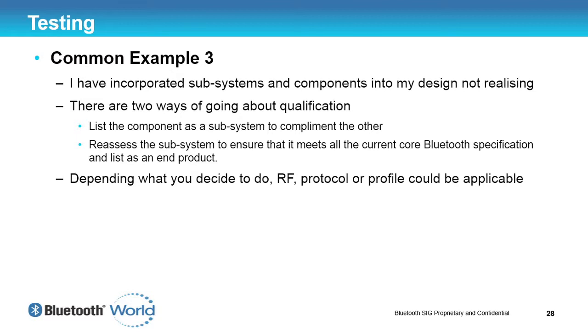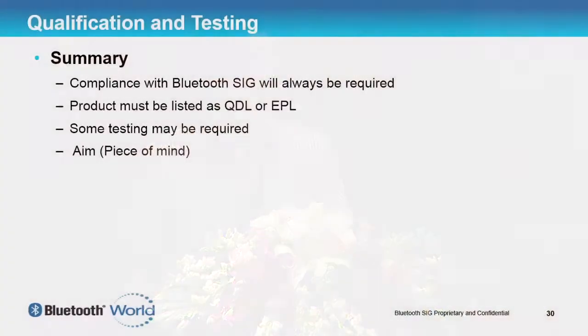A third common example is when a manufacturer — particularly one new to Bluetooth qualification — tries to combine a host subsystem and a component. Currently you can't combine components and subsystems, so we have to be clever: either reassess the host subsystem to ensure it still meets the new qualification requirements, or list the component as a subsystem and combine it with the previous subsystem. You may have to do profile testing, protocol testing, and ensure compliance with the core specification.